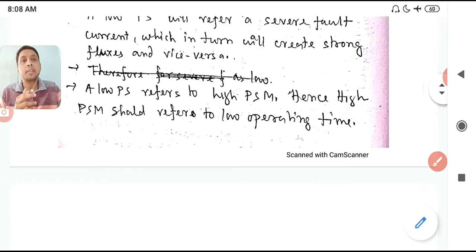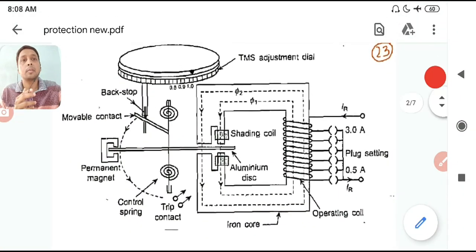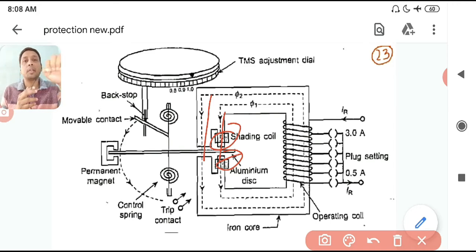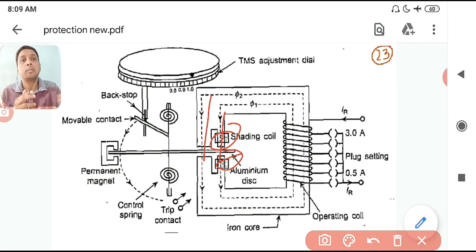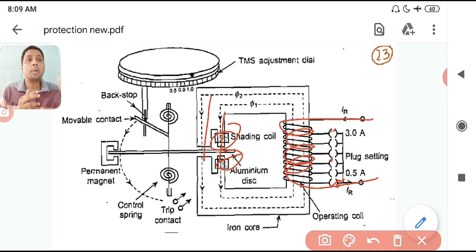Now let us see the figure. You can see the two fluxes φ1 and φ2. Here you can see the shading coil — these are shorted copper bars connected across the pole to create the phase difference between φ1 and φ2, similar to the shaded pole concept. The CT secondary current, which is the fault current, passes through this coil, and here are the plug settings.